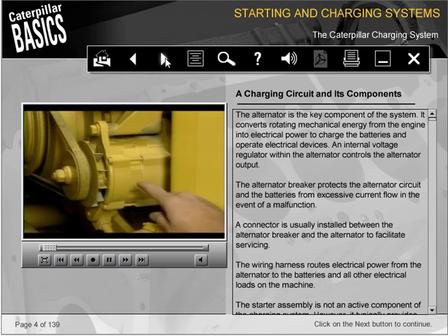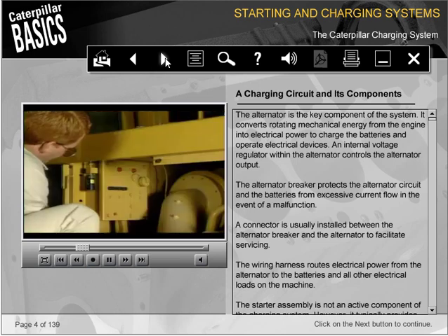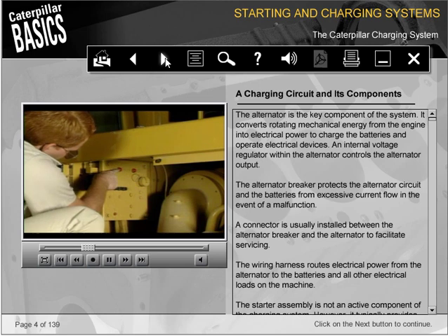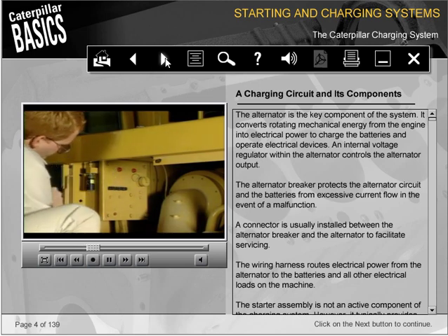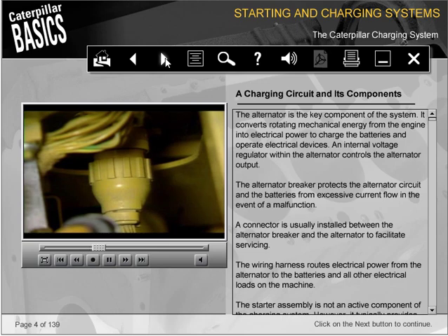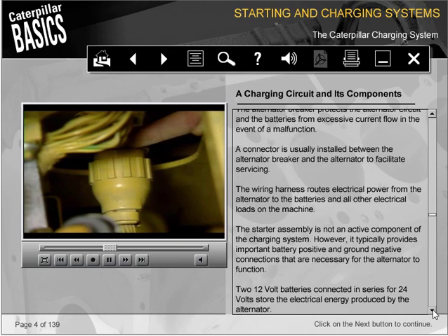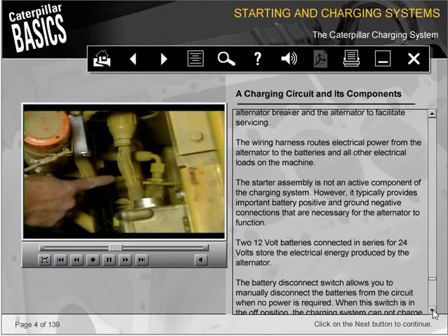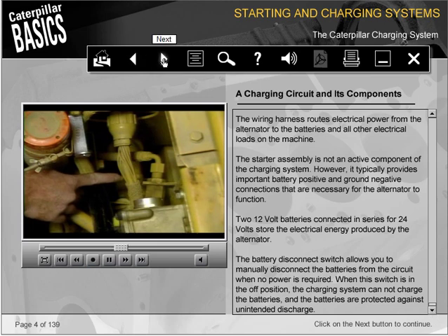The alternator is the key component of the system. It converts rotating mechanical energy from the engine into electrical power to charge the batteries and operate electrical devices. An internal voltage regulator within the alternator controls the alternator output. The alternator breaker protects the alternator circuit and the batteries from excessive current flow in the event of a malfunction. A connector is usually installed between the alternator breaker and the alternator to facilitate servicing. The wiring harness routes electrical power from the alternator to the batteries and all other electrical loads on the machine.